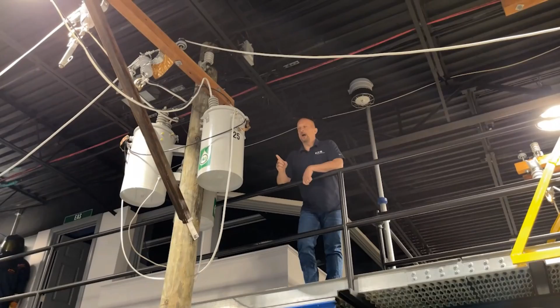Hey, I'm up here. So these ones are a little different. Now, again, don't try this at home. I just happen to be up there because I know these aren't energized. But if you look at these transformers, it has 25 kVA. So three of them together make a bank in a delta Y configuration of 13,800 volts in this case to 480 volts, Y connected, so 480, 277. And this one's going to be solidly grounded. And I'm standing right up here next to the nameplate. So I'll show you a picture of the nameplate in the PowerPoint.